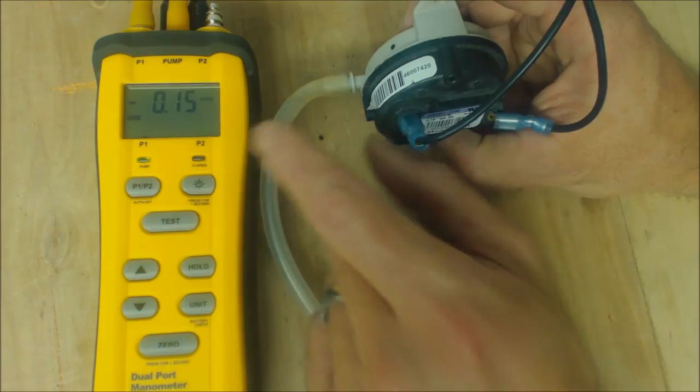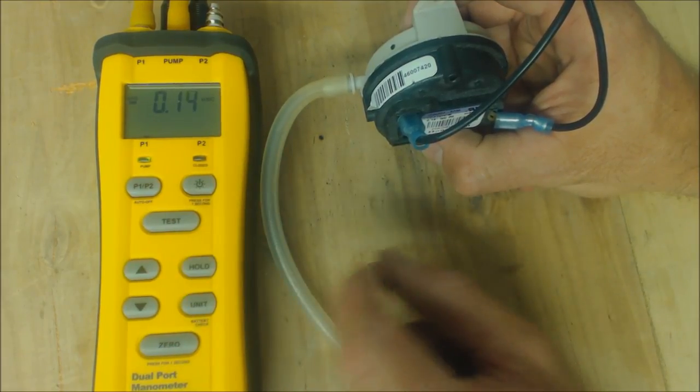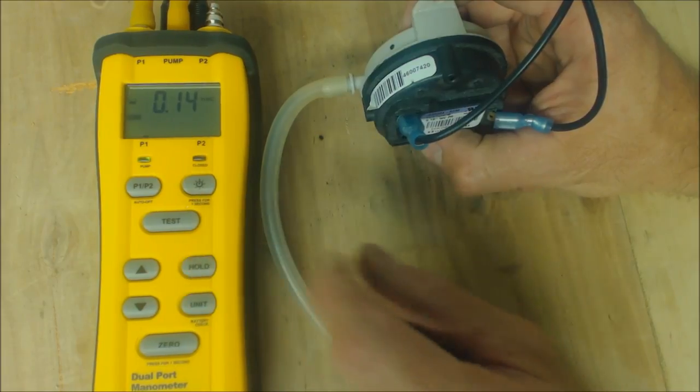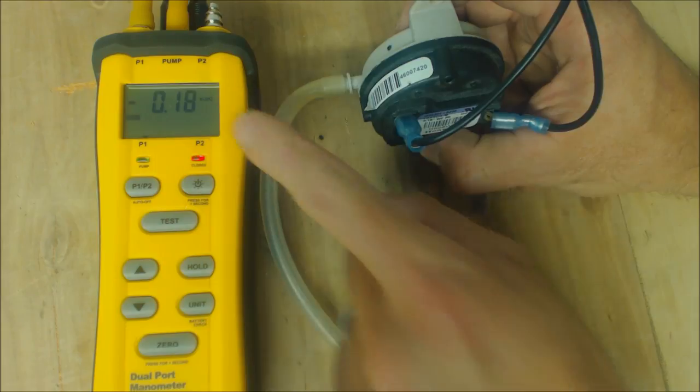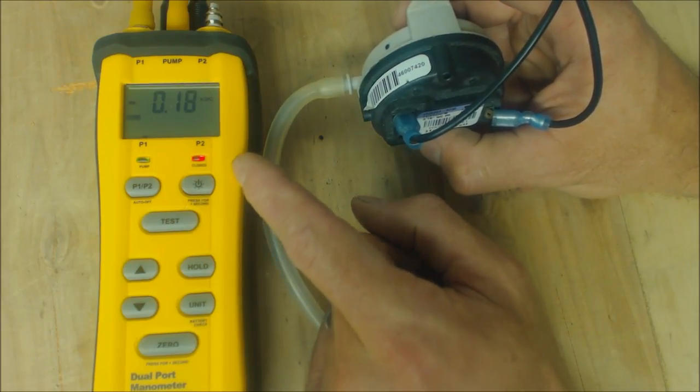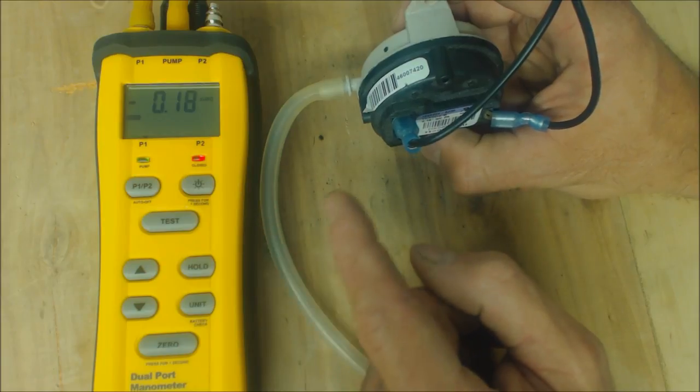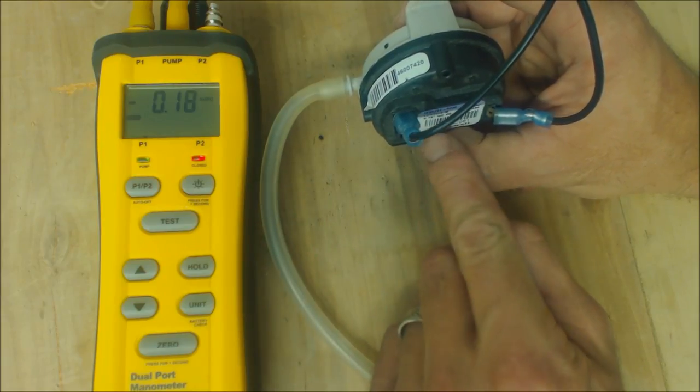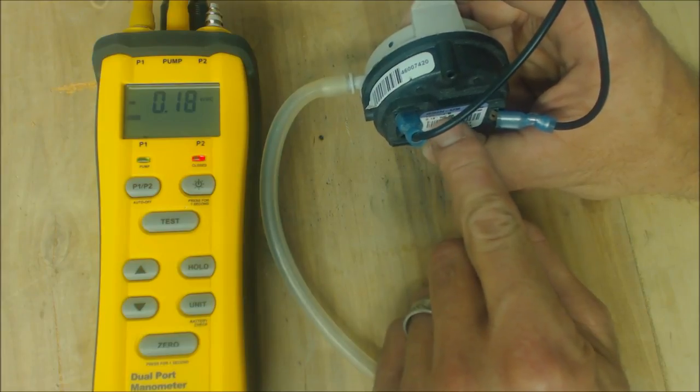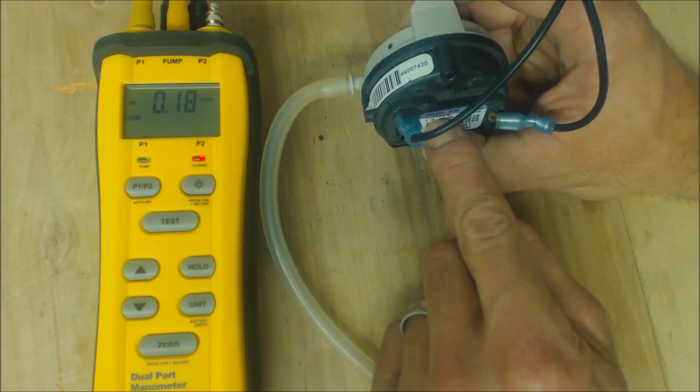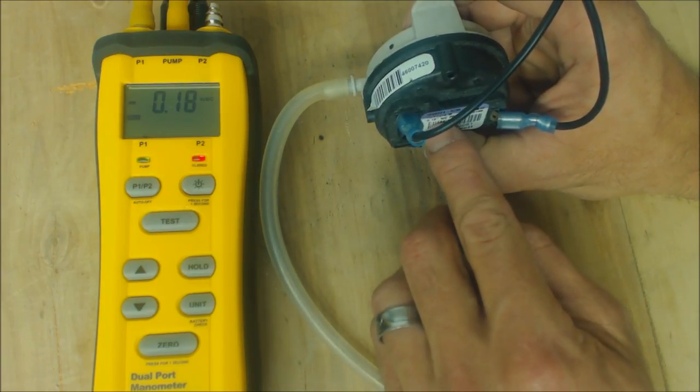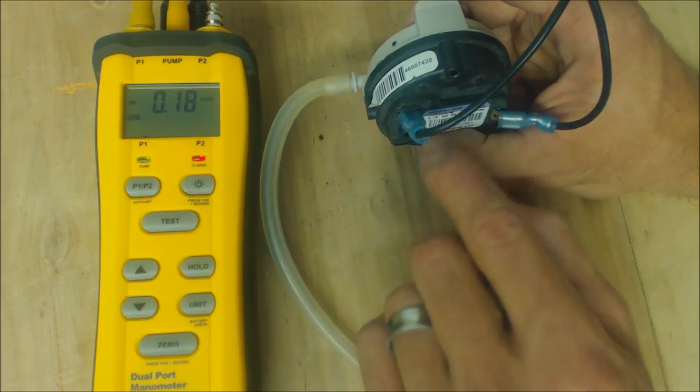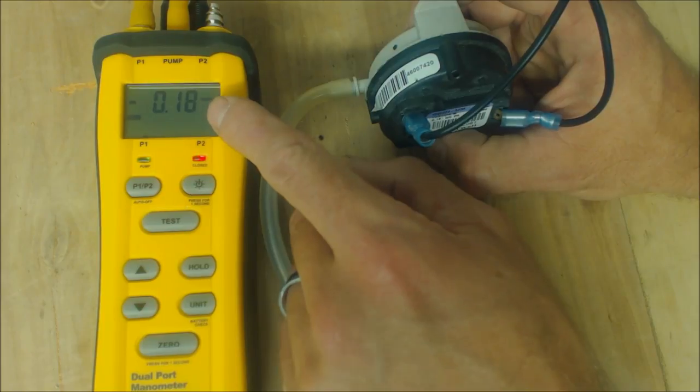You see that little button where it says 'closed' is now not lit. Once again we'll press hold to unhold it, press hold again—now it's flashing. We'll go back up and see what pressure it's going to close the electrical switch at. That time it was 0.18. So the first time it closed at 0.14, when it opened at 0.15, and now it closes at 0.18. That's about the tolerance of this—a very small negative pressure reading.